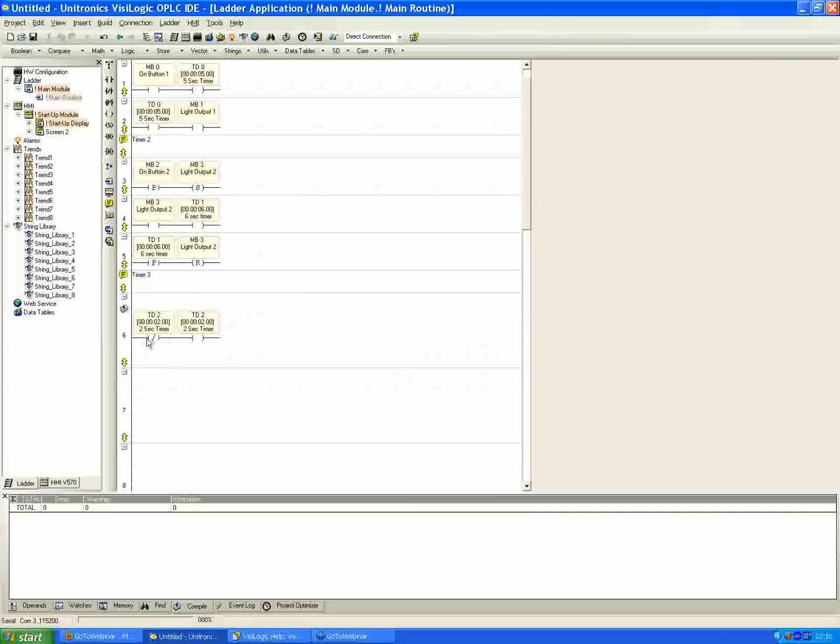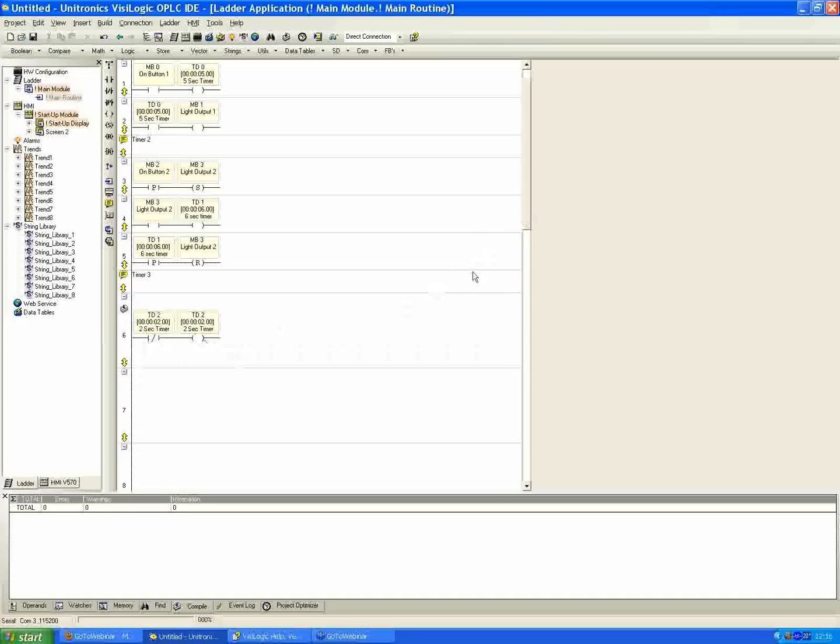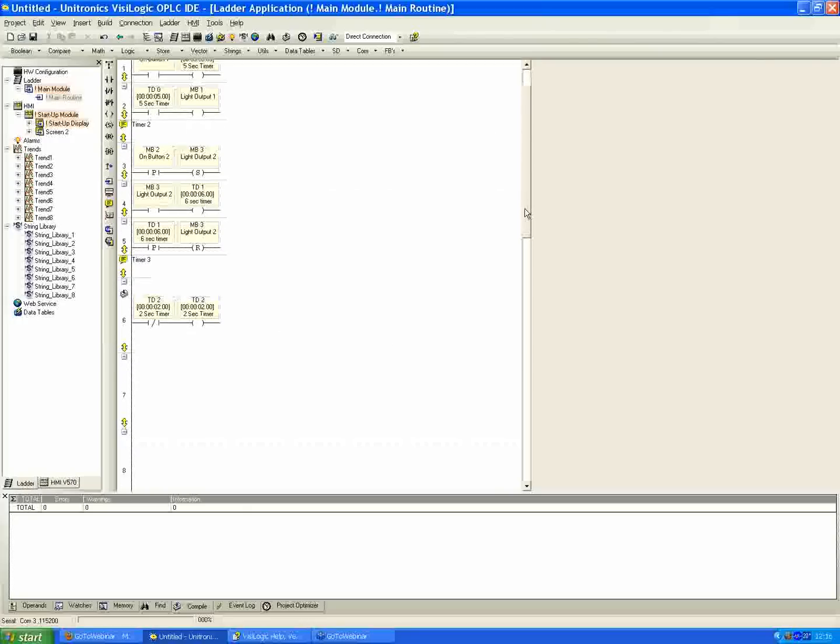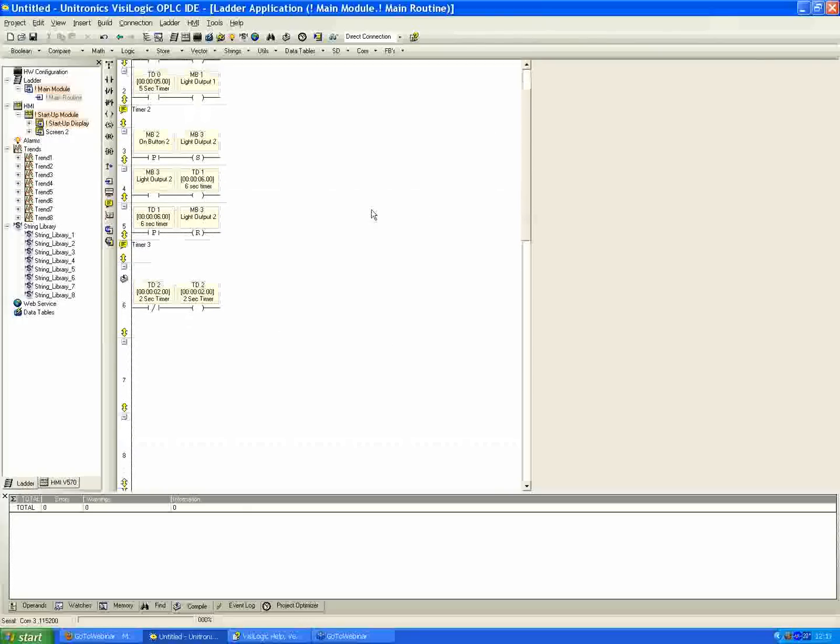This net is going to allow us to be able to count down, enable, energize the timer here, so long as it's not currently active. This inverted contact and then the direct coil allows us to have a timer that's continuously cycling back and forth and counting down. The bit goes high, it does its condition, and then we're going to just start over and do it all again.